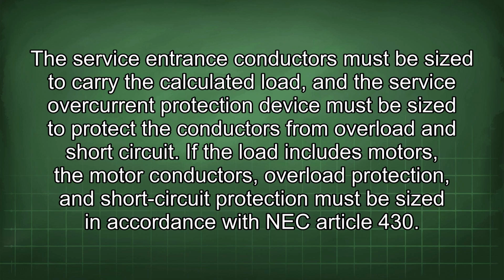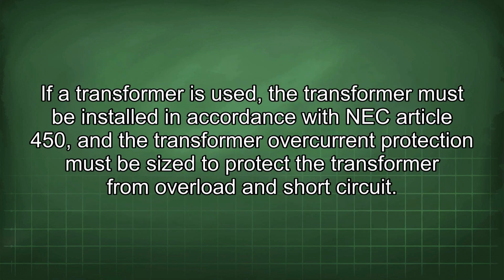The service entrance conductors must be sized to carry the calculated load, and the service overcurrent protection device must be sized to protect the conductors from overload and short circuit. If the load includes motors, the motor conductors, overload protection, and short circuit protection must be sized in accordance with NEC Article 430. If a transformer is used, the transformer must be installed in accordance with NEC Article 450, and the transformer overcurrent protection must be sized to protect the transformer from overload and short circuit.